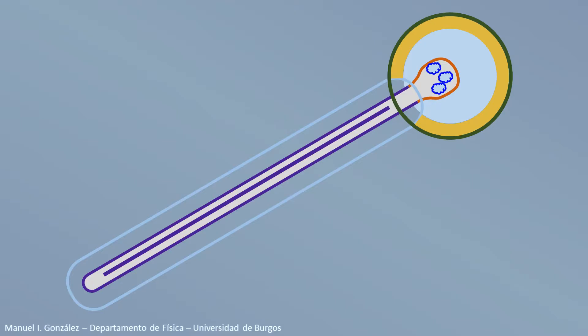As we saw before, water at relatively low temperature circulates outside the bulge. Therefore, the fluid transfers its latent heat to the water and condenses. The bulge is intended to increase the heat transfer surface, so thermal exchange is more efficient.